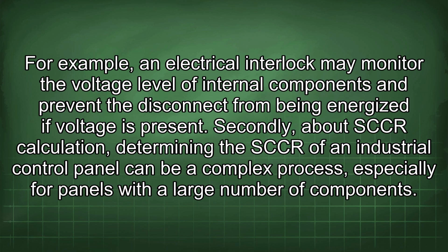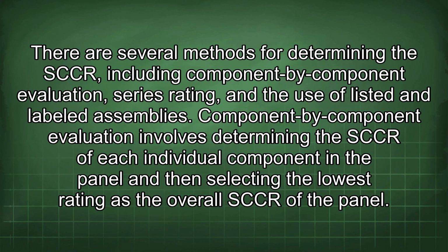For example, an electrical interlock may monitor the voltage level of internal components and prevent the disconnect from being energized if voltage is present. Secondly, about SCCR calculation, determining the SCCR of an industrial control panel can be a complex process, especially for panels with a large number of components. There are several methods for determining the SCCR, including component-by-component evaluation, series rating, and the use of listed and labeled assemblies. Component-by-component evaluation involves determining the SCCR of each individual component in a panel and then selecting the lowest rating as the overall SCCR of the panel.